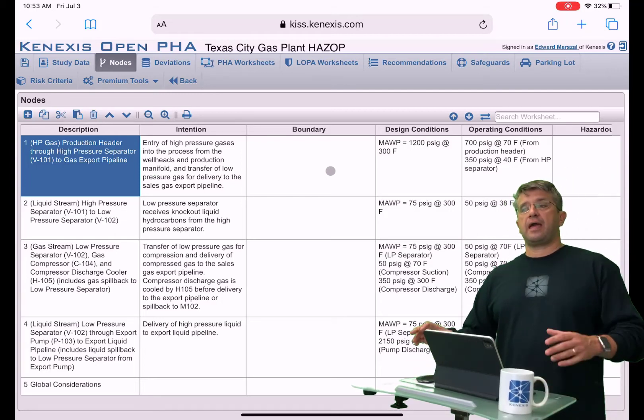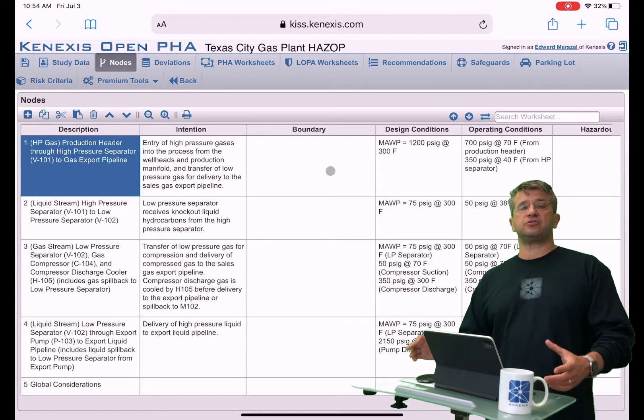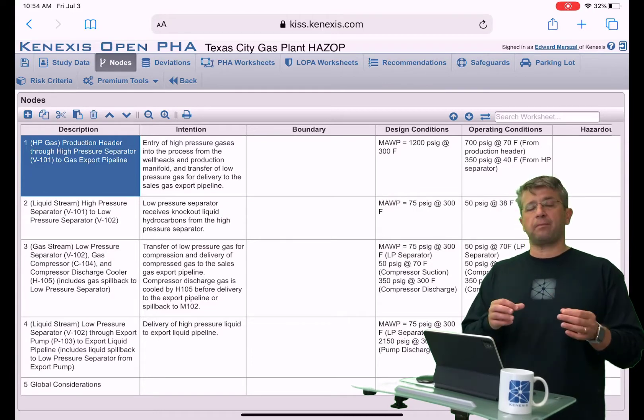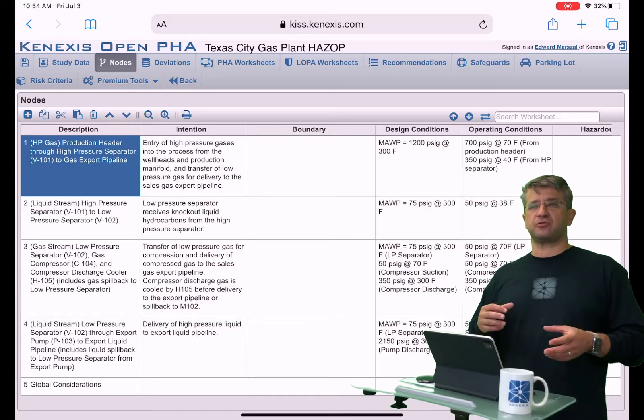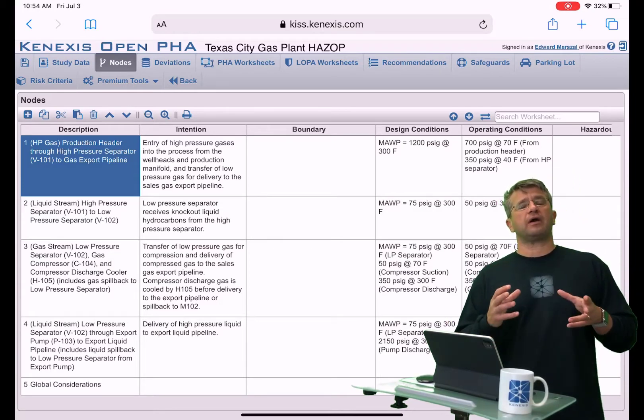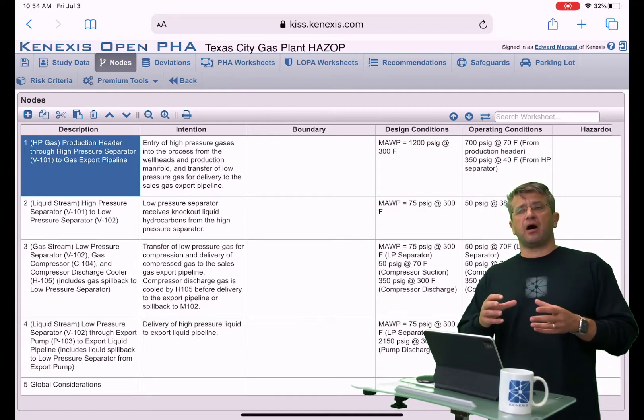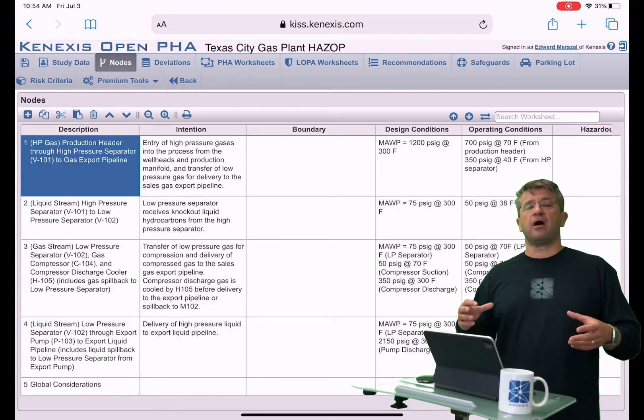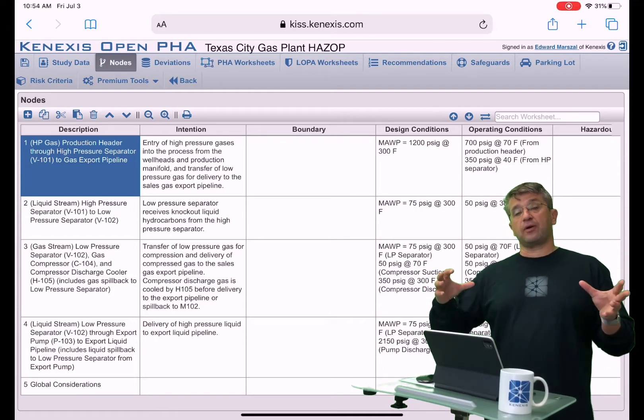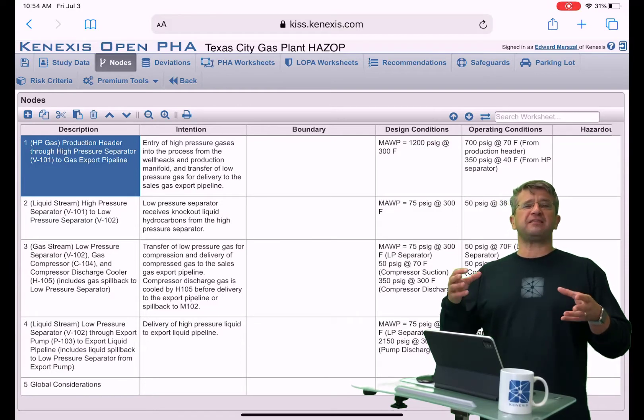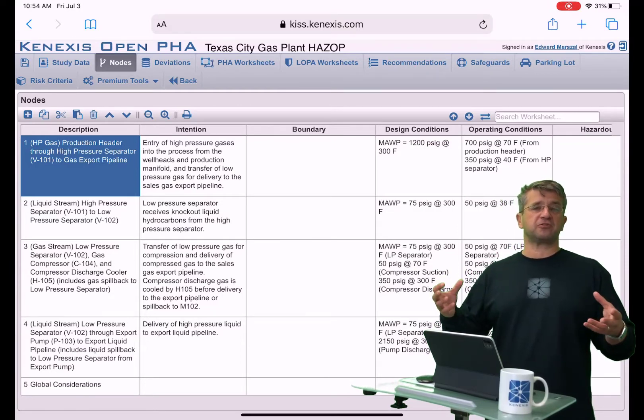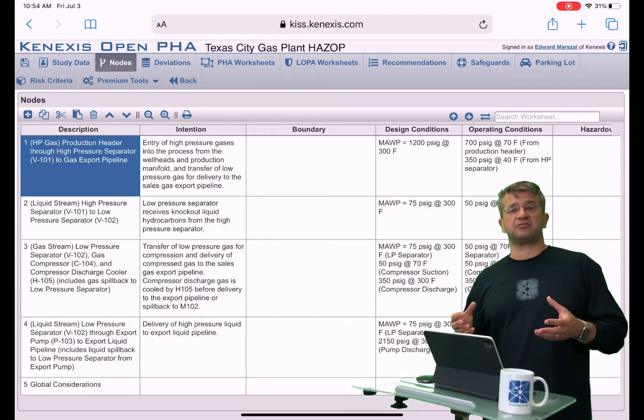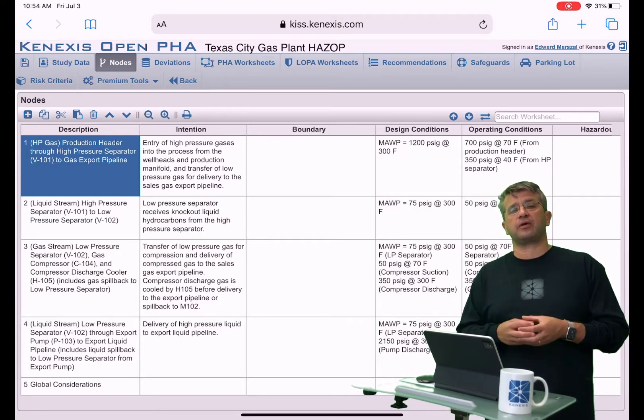In a PHA study, an overall process plant is generally broken down into collections of equipment, as opposed to looking at one equipment item or one pipe segment at a time, which would be prohibitively time-consuming and very repetitive. Instead, a collection of equipment items and their associated appurtenances and piping are looked at together. You're going to define nodes so that they all have roughly the same operating parameters associated with them, and defining those nodes is the starting point for a process hazards analysis.